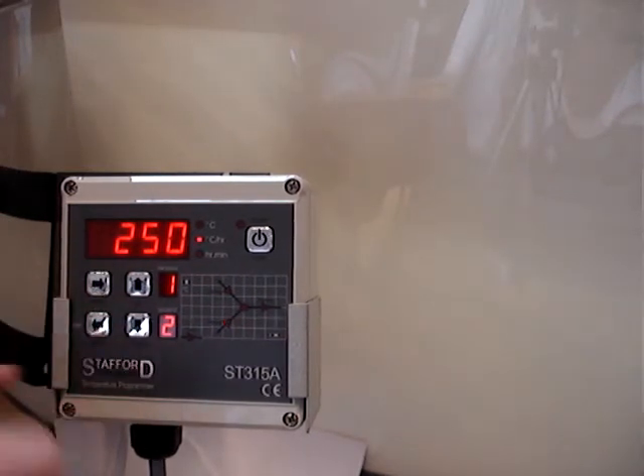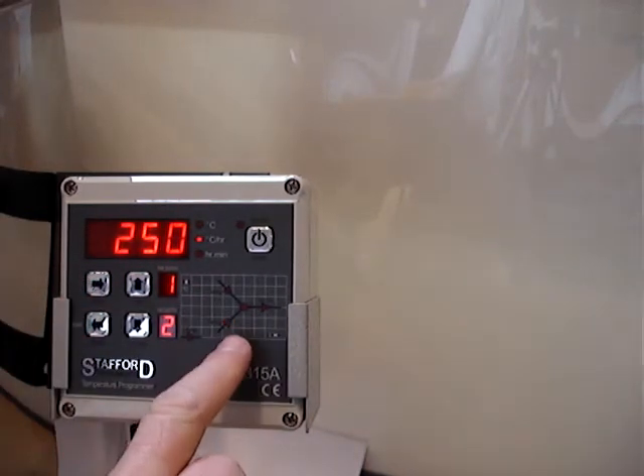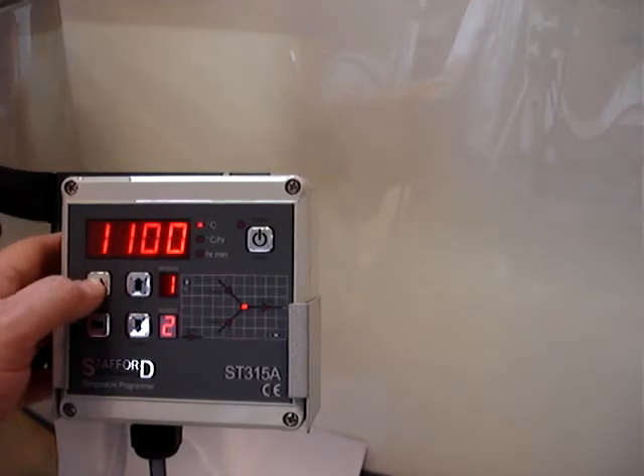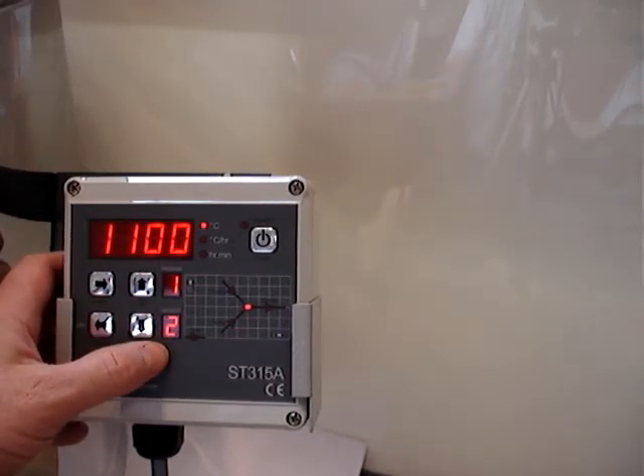So the second climb speed, which is now shown in segment 2, is currently 250 degrees an hour, and that's a heating ramp, as indicated by the light. Our top temperature in this particular case, on segment 2, is 1100 degrees C.